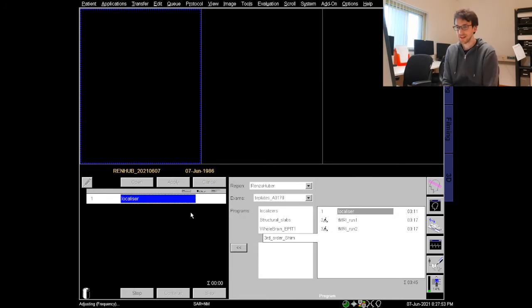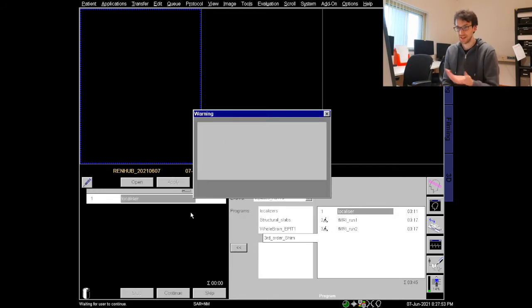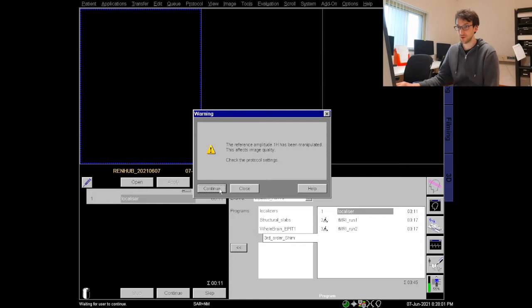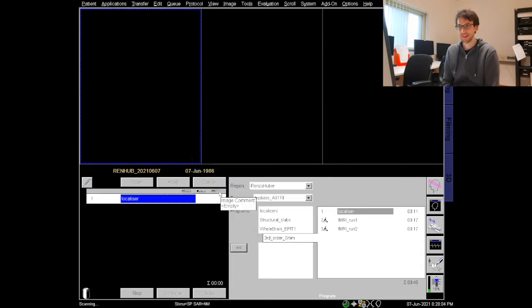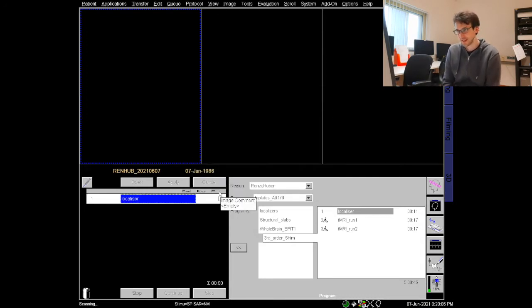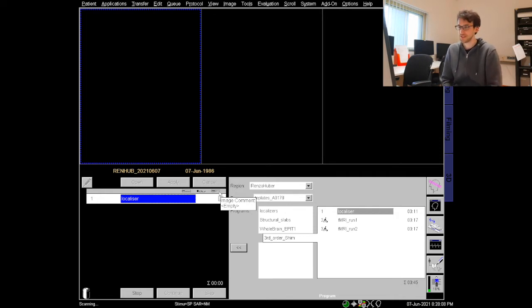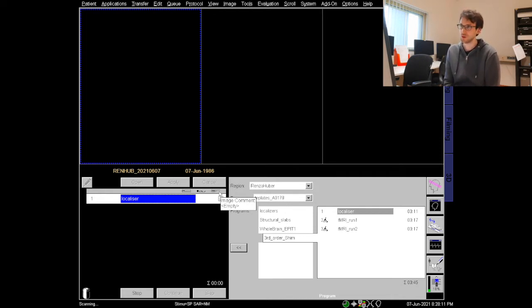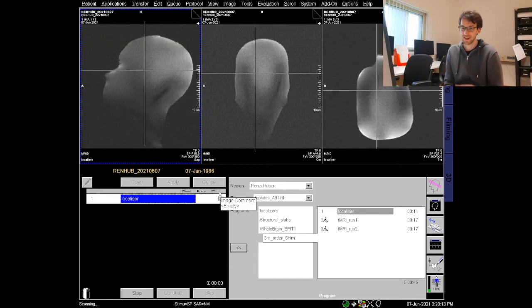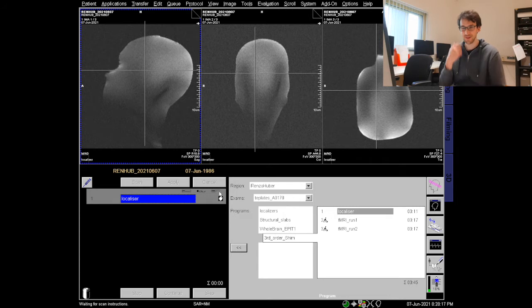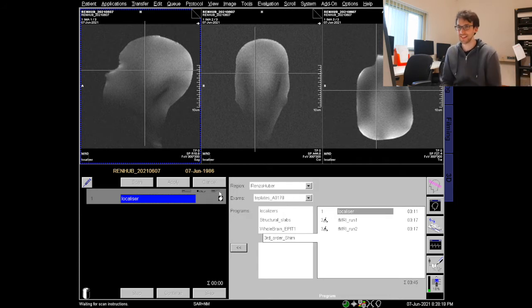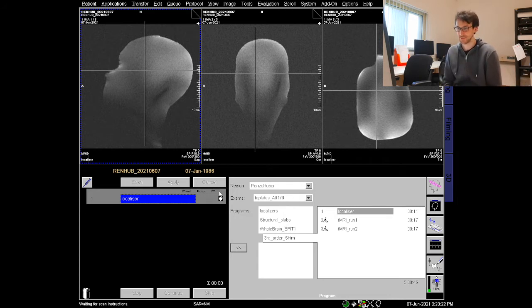Now it usually spits out a few warnings. For example, the one that my transmit voltage has been adjusted. Of course it did because I don't want to do a transmit adjust for the localizer so I click it twice. Then maybe the next one. Okay this was it in terms of warnings. Sometimes there are warnings about peripheral nerve stimulation very often and you can just click them okay because in our common practice at Scannexus we tell the participant before they go in that they might experience peripheral nerve stimulation.